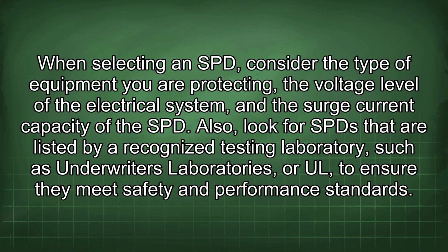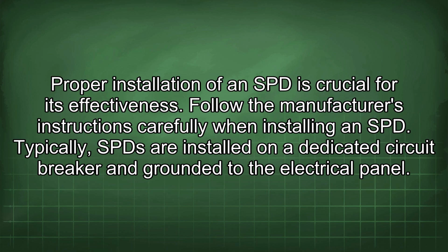When selecting an SPD, consider the type of equipment you are protecting, the voltage level of the electrical system, and the surge current capacity of the SPD. Also, look for SPD that are listed by a recognized testing laboratory, such as Underwriters Laboratories, or UL, to ensure they meet safety and performance standards. Proper installation of an SPD is crucial for its effectiveness. Follow the manufacturer's instructions carefully when installing an SPD.